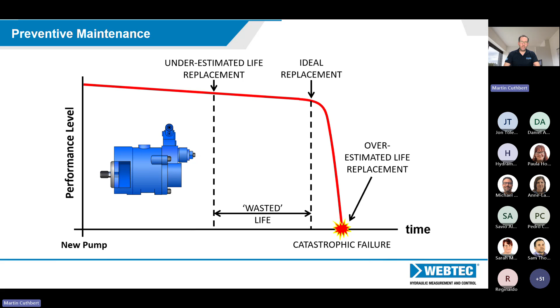If we're not doing real-time condition monitoring, then maybe we can do periodic monitoring. So every 6 months, for example, we might carry out a test on the pump. The advantage of having a tool like the DHM is that you could also record that data, create a little certificate for it and say, okay, that pump on that day performed like this. That gives you a reference point that you can then compare back against. So when you carry out the test 6 months later, you can look at it and say, okay, it's still roughly the same performance. I'm happy, or the performance is certainly starting to degrade. I need to change it.